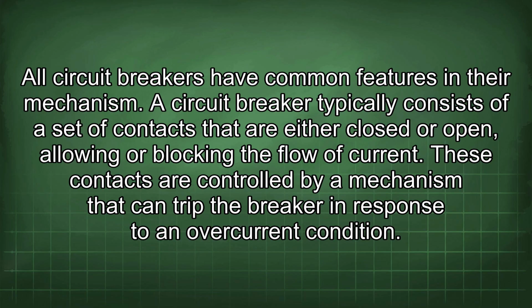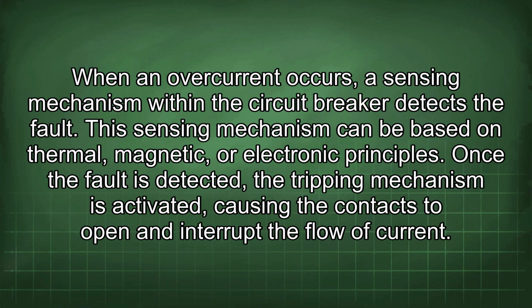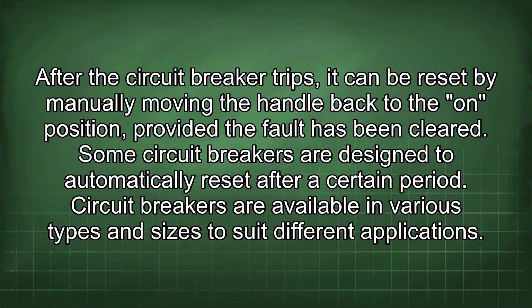All circuit breakers have common features in their mechanism. A circuit breaker typically consists of a set of contacts that are either closed or open, allowing or blocking the flow of current. These contacts are controlled by a mechanism that can trip the breaker in response to an overcurrent condition. When an overcurrent occurs, a sensing mechanism within the circuit breaker detects the fault. This sensing mechanism can be based on thermal, magnetic, or electronic principles. Once the fault is detected, the tripping mechanism is activated, causing the contacts to open and interrupt the flow of current. After the circuit breaker trips, it can be reset by manually moving the handle back to the on position, provided the fault has been cleared. Some circuit breakers are designed to automatically reset after a certain period.